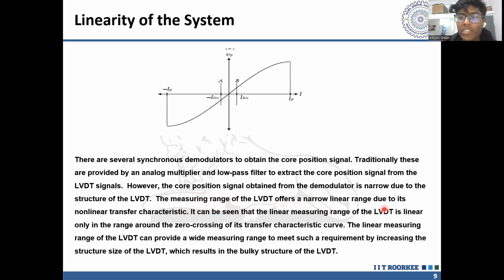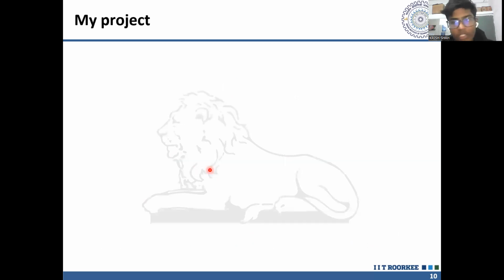The measuring range of the LVDT offers a narrow linear range due to its non-linear transfer characteristics. What do we mean by non-linear transfer characteristics? These demodulators that are being used work on a transfer function, and this transfer function has a very short range. It can be seen that the measuring range is linear only around the zero crossing of its transfer characteristic curve. This is obvious. The linear measuring range of the LVDT can be widened to meet such requirements by increasing the structure size of the LVDT. But as mentioned earlier, it is not feasible in many cases. So my project that I am currently working on is about how to increase the range of an LVDT of a particular size just by changing the demodulator circuitry.